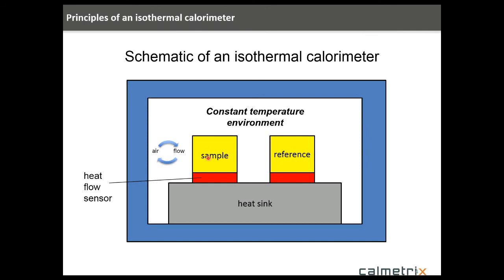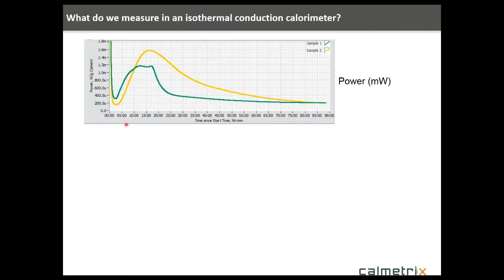But in the case of a sample giving off heat, basically what happens is that the heat flows from the sample into the heat sink, and the heat flow sensors can sense that. The raw signal of these heat flow sensors, which are basically thermoelectric devices, is a voltage signal, and during the manufacturing process we basically calibrate and relate that voltage signal to the heat flow in watts from the instrument. So that's basically what we're measuring, is heat flow either into or out of the sample. So the raw data, the data that we get from the instrument, is typically shown here in power and watts, though typically we will normalize that signal per gram of sample. So typically we are plotting watts per gram as a function of time.